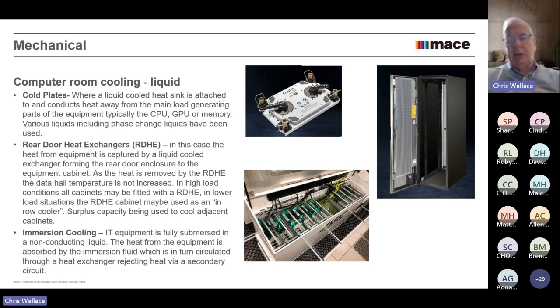As well as that, you'll need some circulation space, and you need maintenance space. So if you can get rid of all that, and you can use the aisle between the two rows of equipment, and you don't need any hot aisle containment, to actually use as a maintenance space for the rear door heat exchanger, you can actually either narrow down the size of your data hall, or have more capacity in a given size of floor area. These have been used as a retrofit as well. I think, as you can probably hear from my enthusiasm, they're more and more popular.